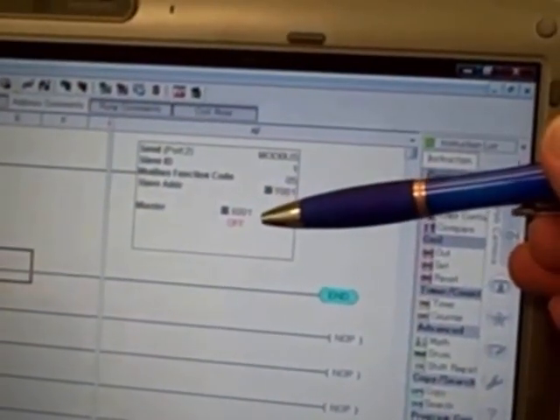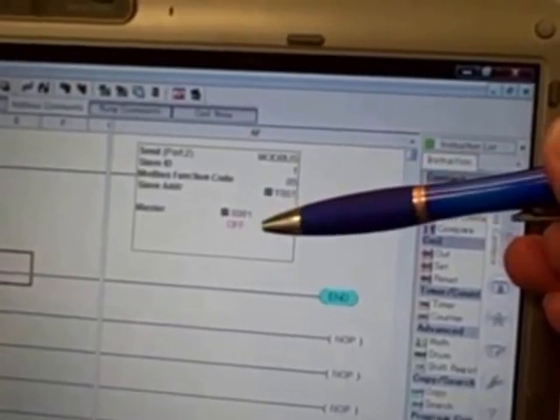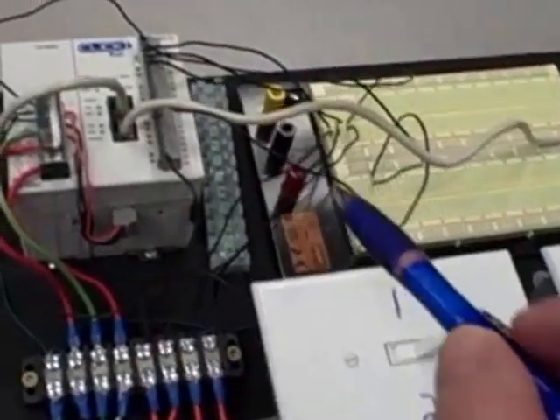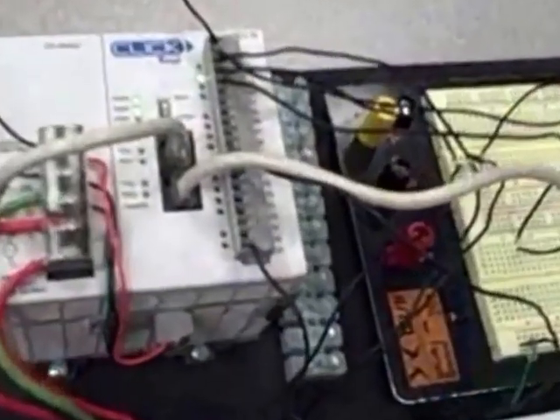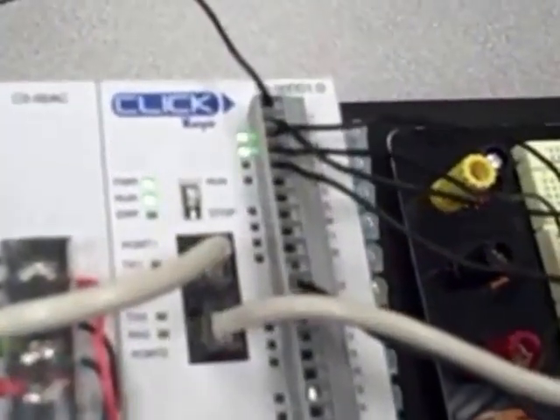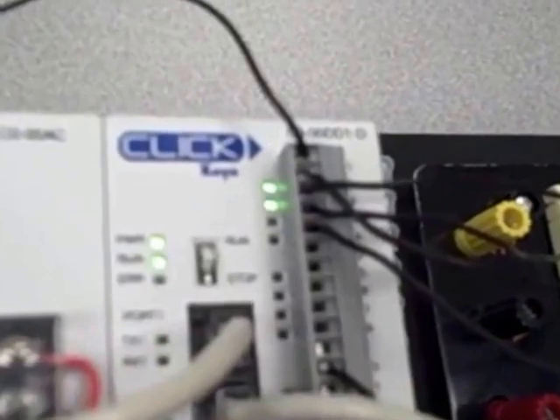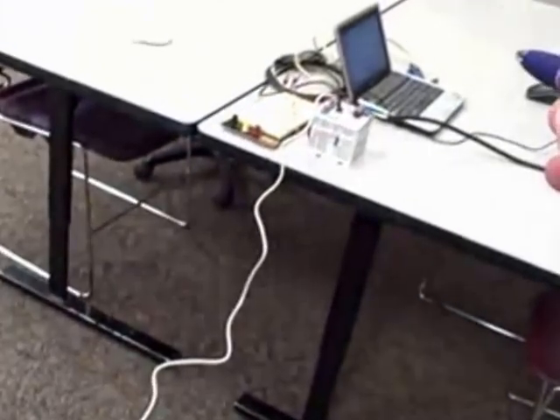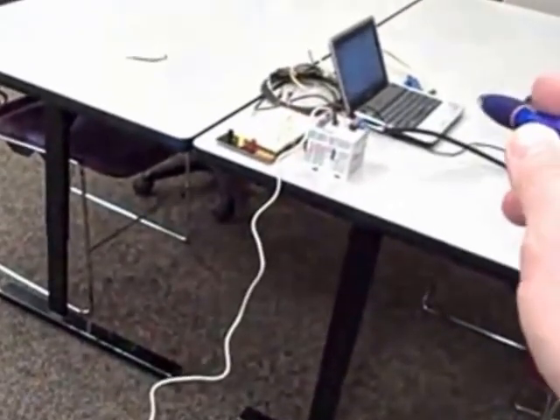Over here the input where it gets the bit information to put into coil Y1 is the X1 input of the master PLC. So the idea is when I flip X1 on and off in this PLC, as you can see the green light coming on right there in channel X1, that it should drive the Y output number 1 on the slave PLC.